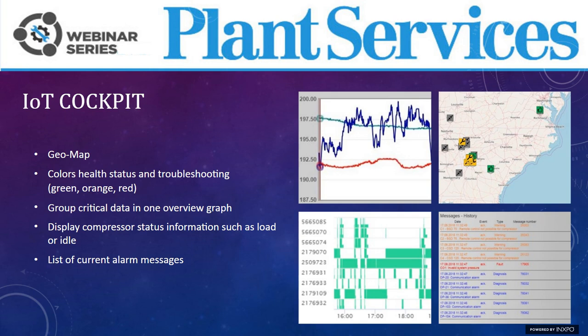Let's take a look here at an IoT cockpit, and this is really an example. IoT cockpits should not be limited to web browsers. Rather, they should be accessible via mobile app or with push notification. And I would like to add, they should be available for tablets as well. It's good practice to have a geomap for different locations. Also, use a color code for station health status. That helps with an overview. And good practice is to have red for alarms, orange or yellow for maintenance, and green for status okay.